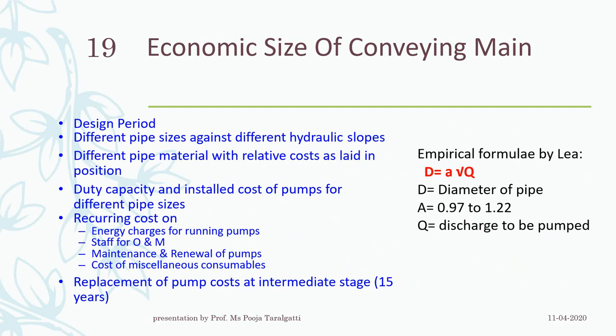Moving forward, what are the considerations needed while designing or calculating the economic size of the conveyance main? First: the design period — how many years you want that particular pipeline to serve. The design period is generally considered as 30 years for a typical pumping main. Second: different pipe sizes against different hydraulic slopes, which comes under topography and design.